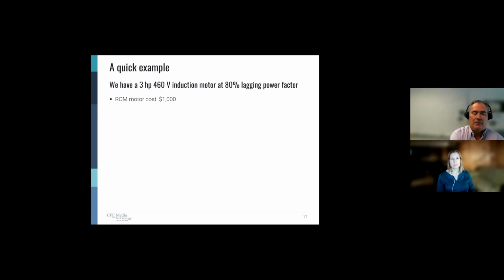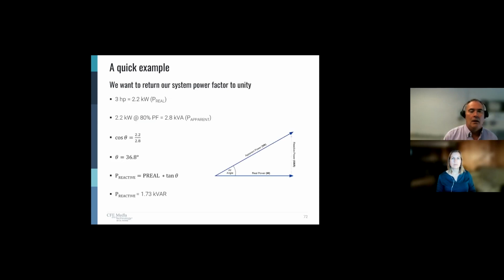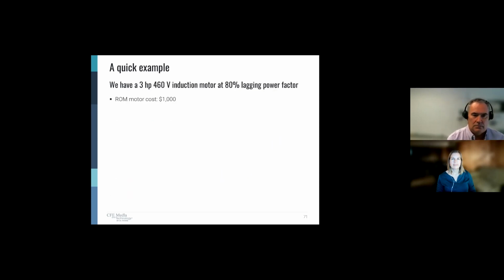So let's give an example here real quickly as we wrap this up. So let's assume we have a 3 horsepower, 460 volt induction motor at 80% lagging power factor. And real quickly, this is a 460 volt motor. Remember that equipment is specified at a lower voltage than service. So a 460 volt motor is intended to run on a 480 volt service. So a 3 horsepower motor, 80% lagging power factor. Rough order of magnitude motor cost, according to our good friends Google, is $1,000.